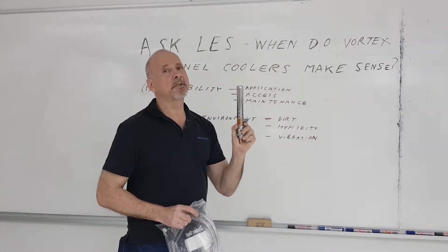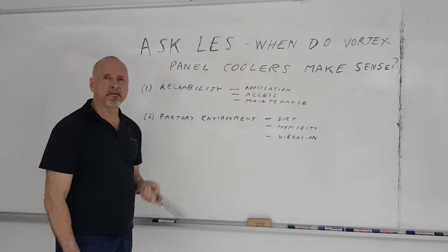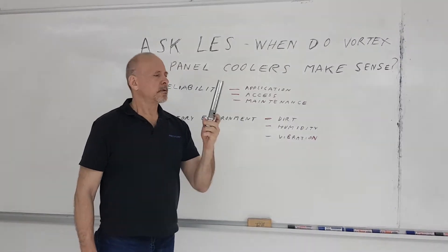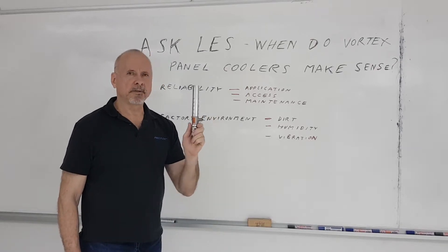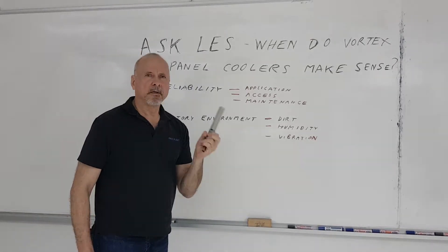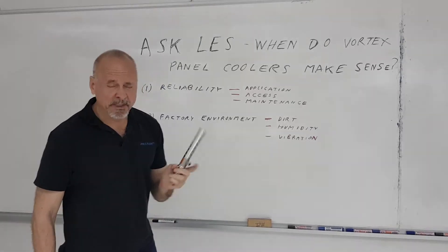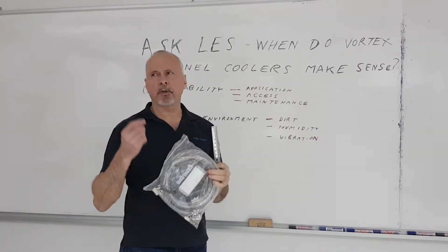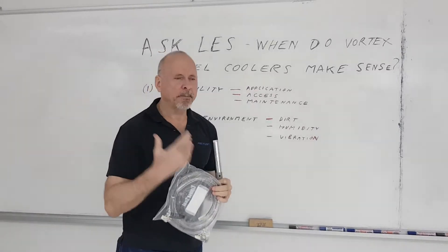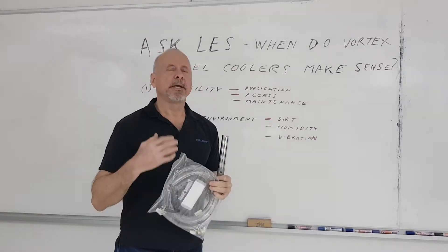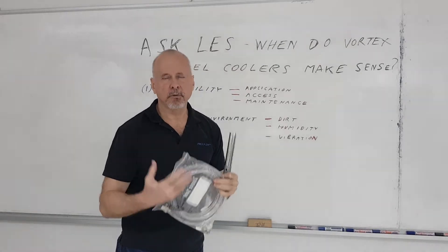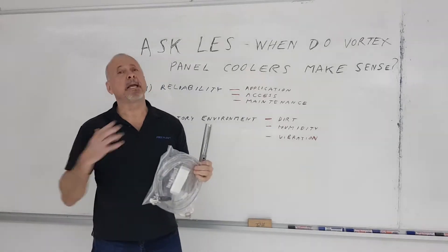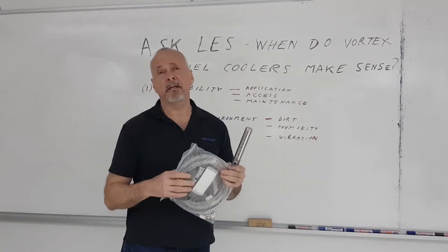Now, the factory environment. The dirtier the environment, the more it makes sense to use a vortex tube operated panel cooler. For example, I was in a factory where they were making a product that put a lot of fiber in the air, and this fiber kept getting into the control panels — they literally had to clean the control panels every single day.